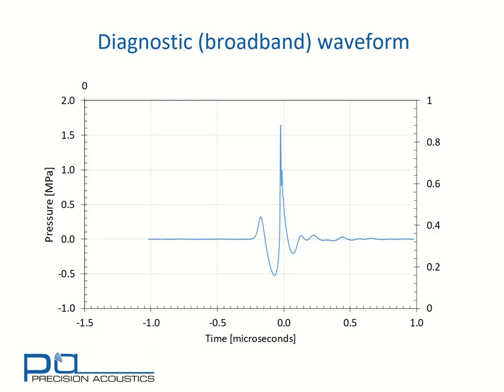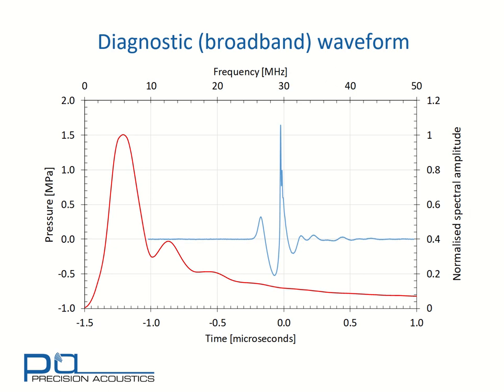We'll contrast this with a very broadband signal. This is typical of what one might see for diagnostic ultrasound, but you can often see other applications in non-destructive testing and lithotripsy, where there are similarly short pulses. In this case, because of the high pressure levels, we also have non-linear acoustic propagation, and this has led to harmonic generation. So we have a very broad band spectrum. Although the peak is about 6 MHz, there is significant spectral content at 20, 30 and even 40 MHz.